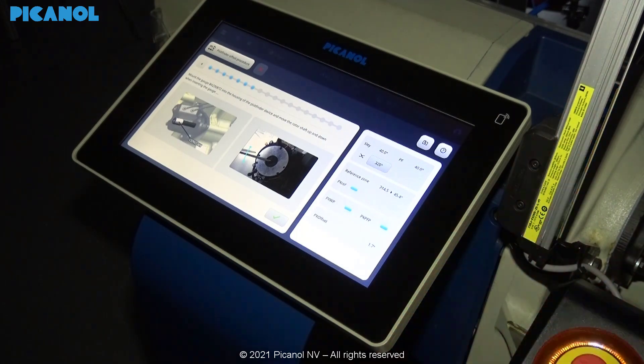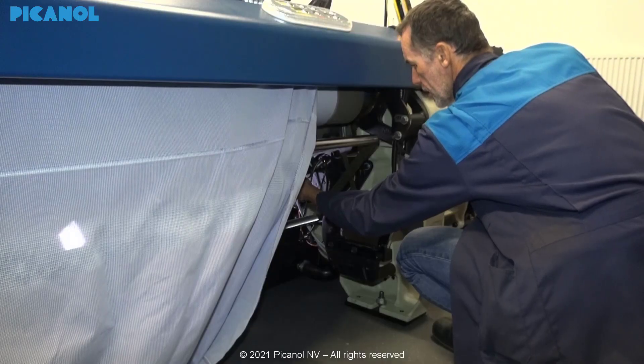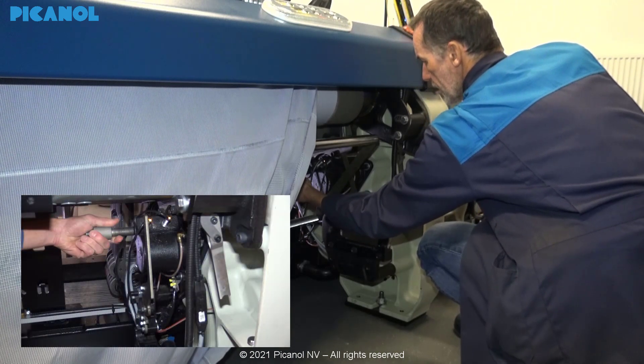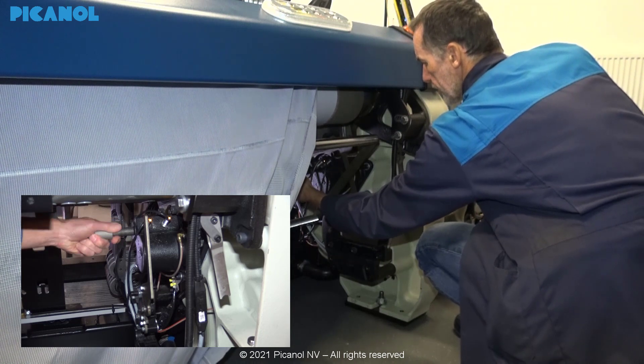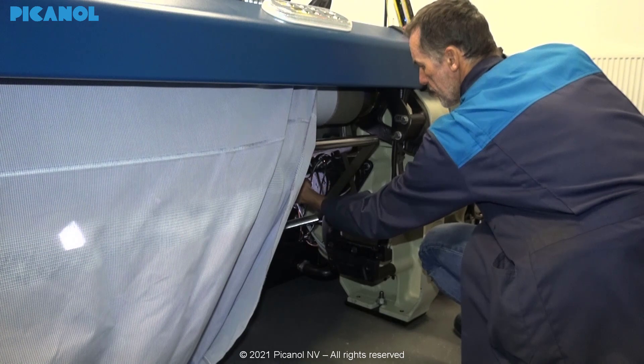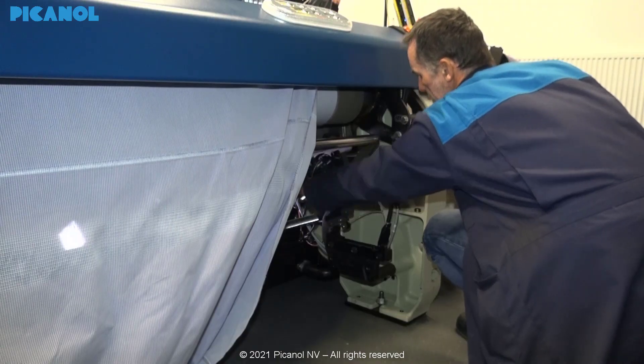Next we are going to enter the gauge into the housing while moving the rotor up and down. Insert the gauge until you feel a certain resistance. You will see you still have around 1 cm of thread left on the gauge. Remember this is just an indication and is not an exact science.